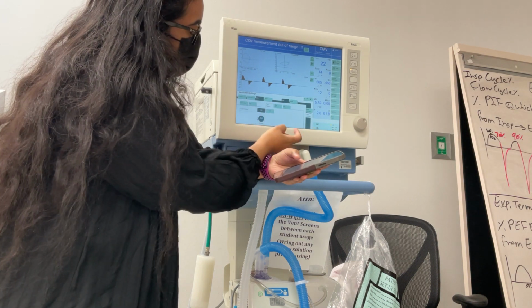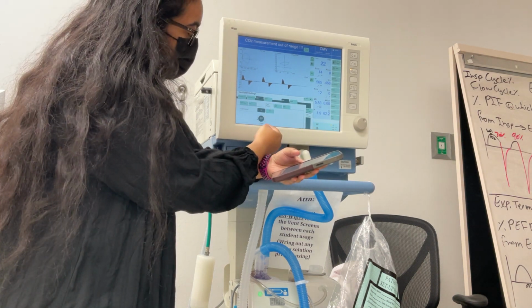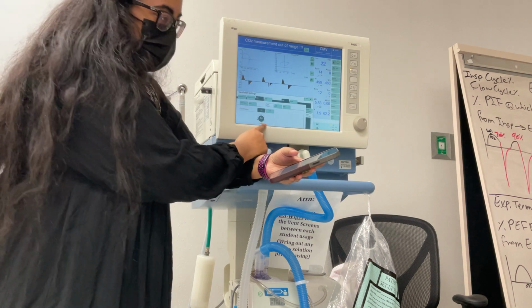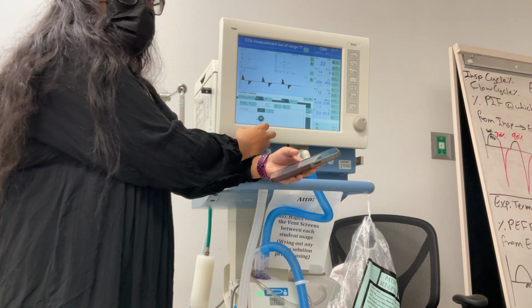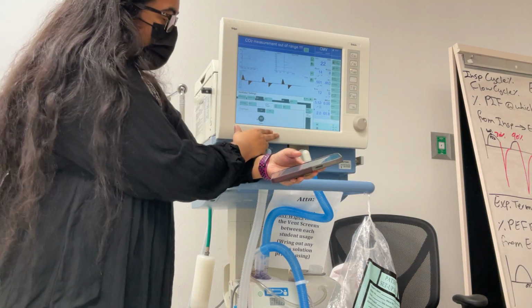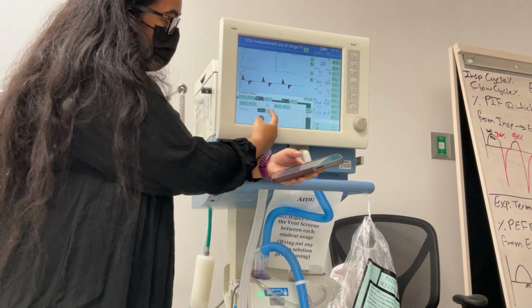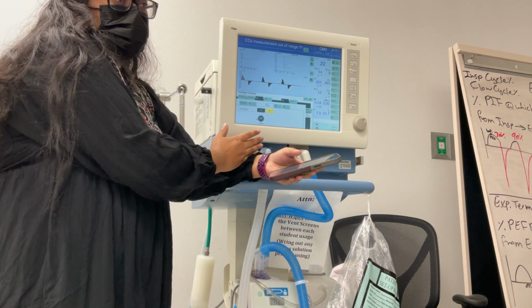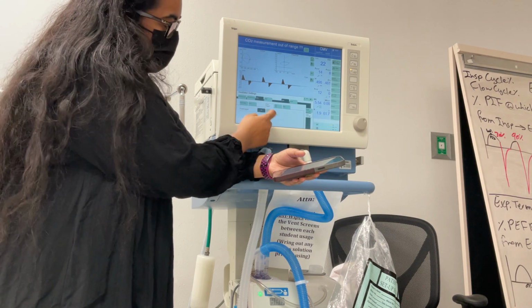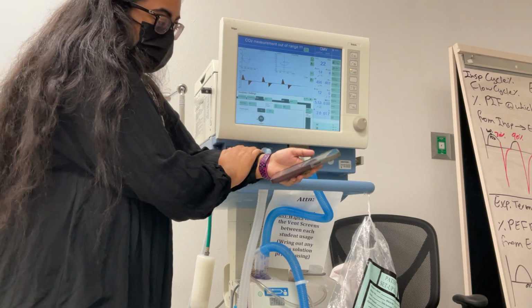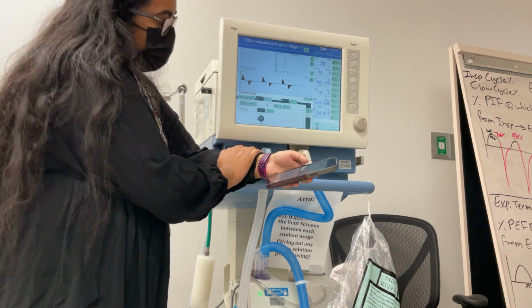On this mode, or on all of them, you'll always see your flow trigger. Flow trigger is the only one that you can actually change on here. Pressure trigger is always on in the background. So on or off, if you turn it off, pressure trigger is still active in this vent. But if it's on, you can adjust that trigger to set it as sensitive as possible without auto trigger.